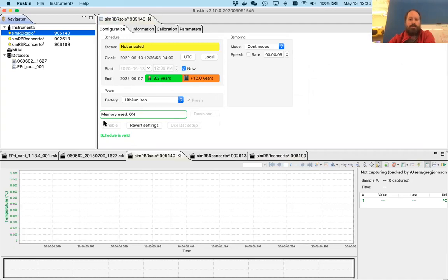So usually once the instrument is running, this download button will be available for you. When you select that, this little progress bar will fill up and the data will come out of the instrument. It's typically over USB, working on your desktop, so it's very quick. You can download over serial, of course, or Wi-Fi or Ethernet. There's no restriction on any of that behavior.